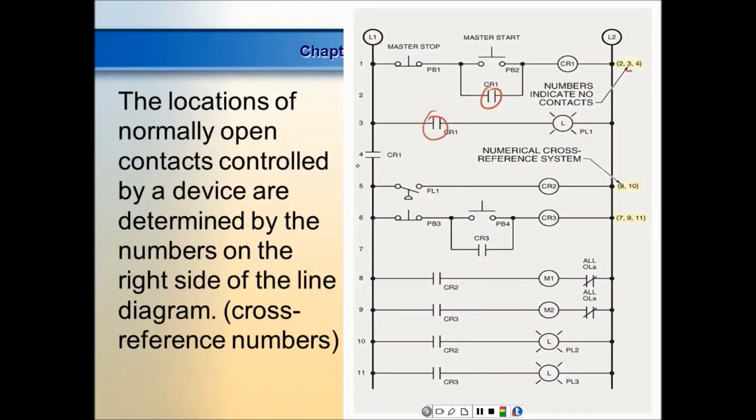I come up here and look at line 4. I go up and look at line 4. There it is. We don't see this normally, but even if we break L1 and L2, it gets a wire number. And there it is right there. I come down here and look at the light bulb. Why aren't there any numbers on the right-hand side of L2 for a light bulb? It has no contacts. Thank you, Nicholas. Hopefully you're not the one that put numbers out there.